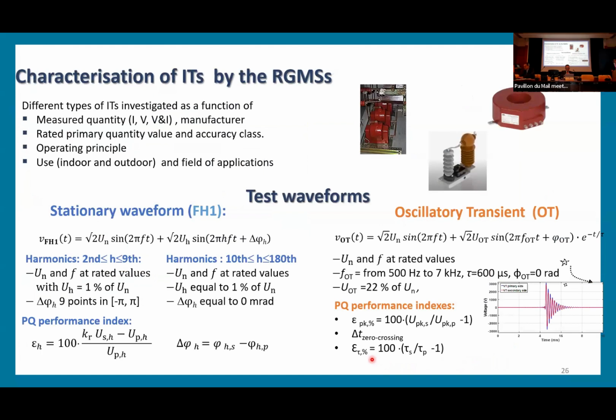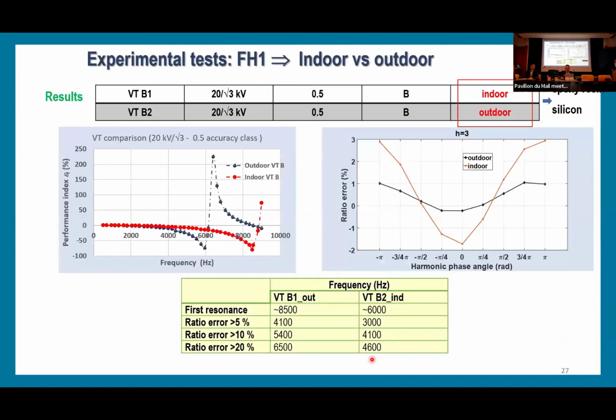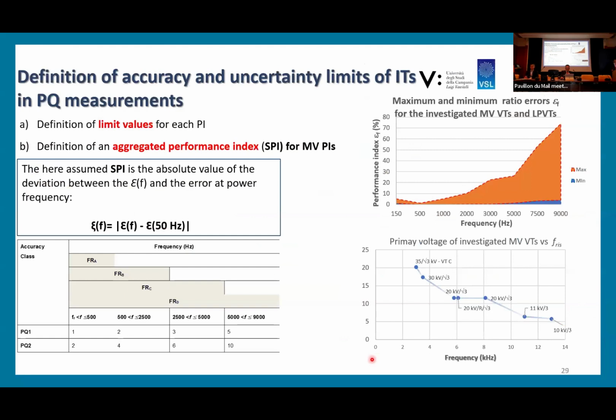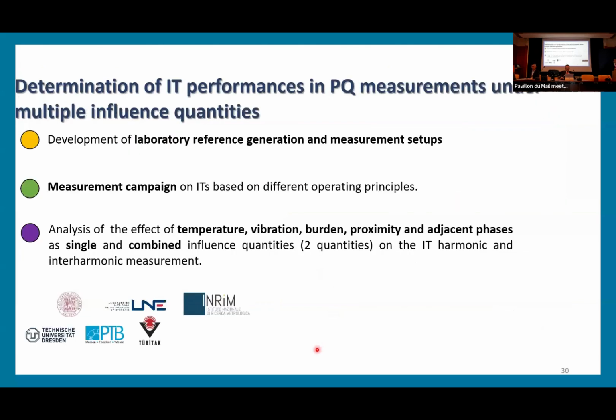All these reference generation and measurement setups were used to characterize a number of commercial devices, in terms of various input rated voltage, outdoor or indoor application, or even different technology. I don't spend too much time on commenting these results since the time runs fast. Another important aspect defined in the IT4PQ project is the definition of an aggregated performance index, something like a PQ accuracy class, so an extension of the classical definition of accuracy class of the instrument transformers, but for power quality measurements.